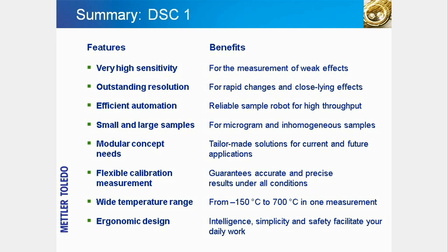This slide summarizes the features and benefits of the DSC-1. The Mettler Toledo DSC-1 measures heat flow very reliably with optimum resolution and sensitivity so that even the weakest effects can be measured. For high throughput applications, a sample robot allows easy automation of entire sample series, and even different types of crucibles can be measured with individual temperature programs. Because of its modular concept, options such as sample changers or cooling devices can be added later. Flexible calibration procedures allow the instrument to be calibrated and adjusted over the entire temperature range from minus 150 to plus 700 degrees Celsius.